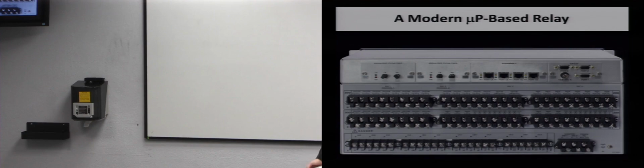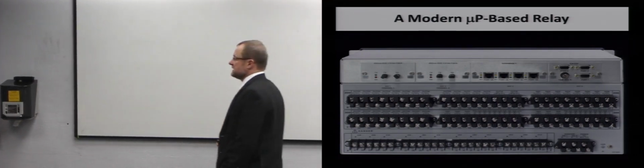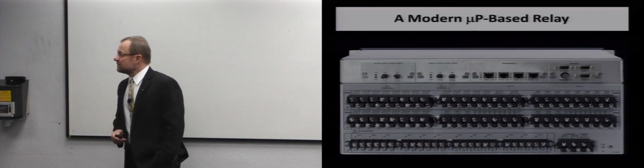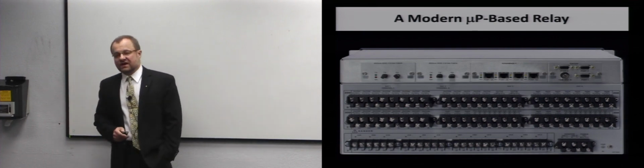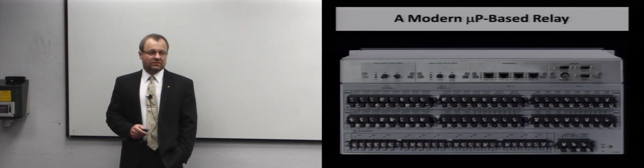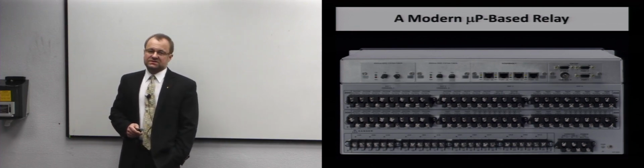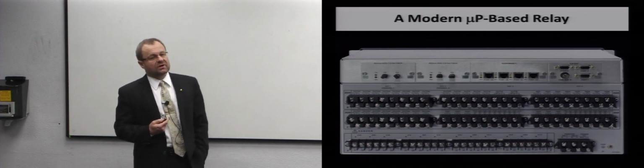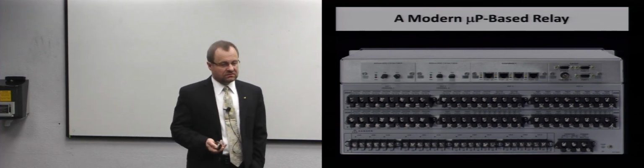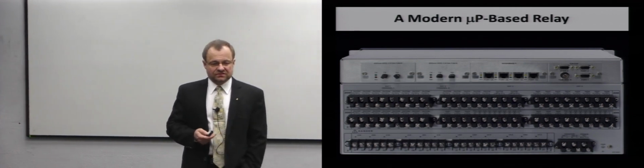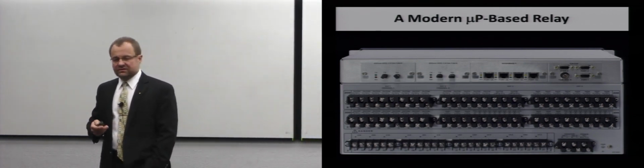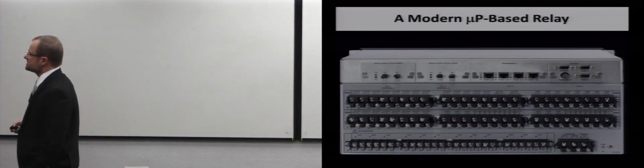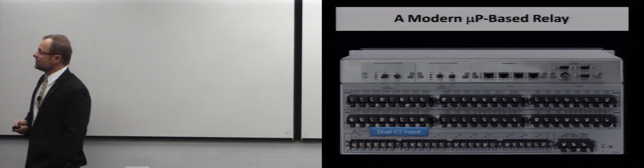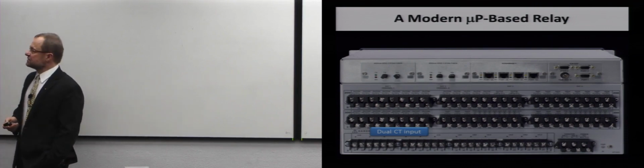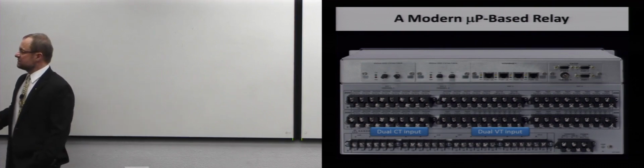When you look from the back, this is where we get our signals. There are new concepts to bring the signals via optical fiber from non-standard voltage and current transformers. But the reality today is that we get our signals through copper connections from a traditional current transformer and voltage transformer, so 5 amp nominal, 110 volts nominal voltage. So you see a lot of screws, and they are for CT inputs. Modern relays could take, say, 2 CT inputs for line protection. You could have dual CT input, and those are 3-phase inputs.